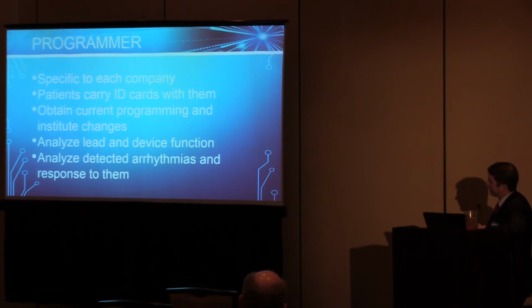Also, if they don't have their ID card present, all the manufacturers, if you Google them online, will have a 1-800 number of some sort that you can call and inquire as to whether the patient belongs to that manufacturer or not. Again, it allows us to look at current programming and the behavior of the pacemaker, as well as institute changes in programming, analyze lead and device function, and analyze any arrhythmias that might be present. These are excellent ways to pick up atrial fibrillation or ventricular tachycardia.